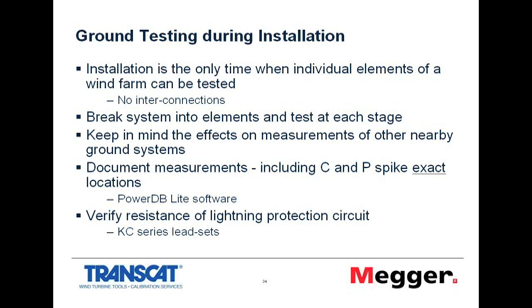We can help you with that in that we have some software which is provided free with many of our instruments, called PowerDB Lite, which is asset management software. The benefit I want to highlight is that there are a number of forms in the software which you can fill in, and the test form will perform the calculations for you. So if you give the form the 3 measurements for the slope method, the form will calculate the actual position for you. You don't have to do the formula or look it up on a chart. It does all that for you, and it does that for a number of methods.